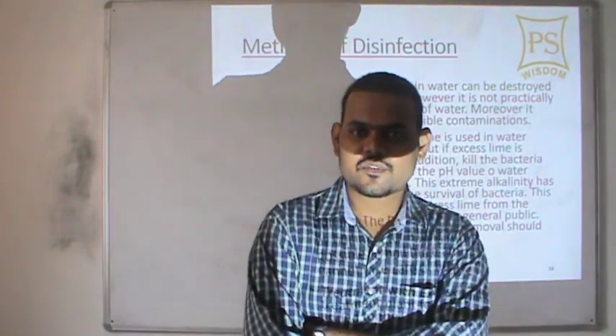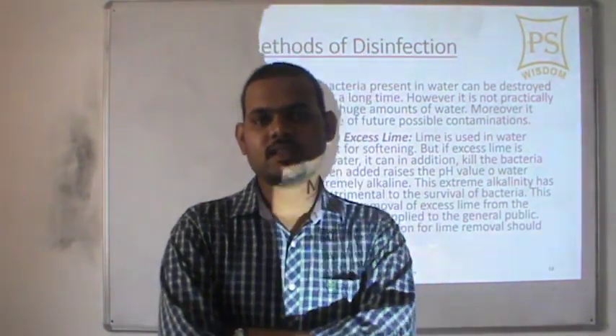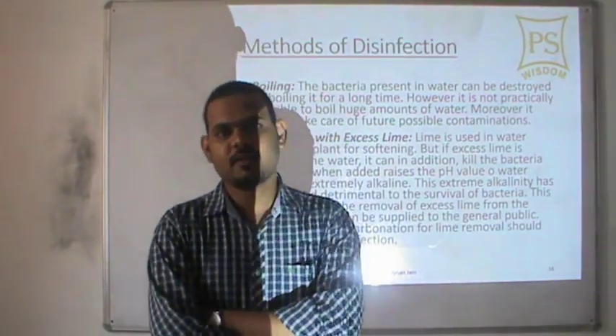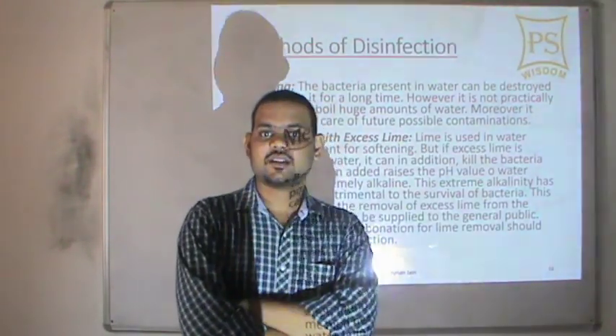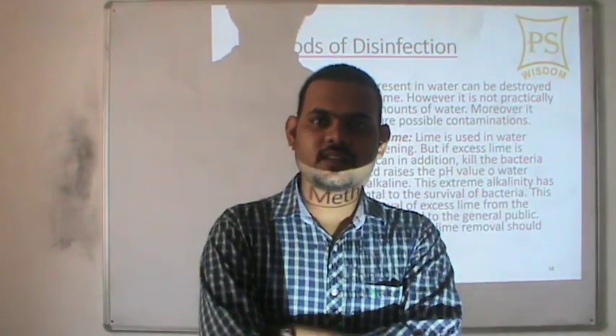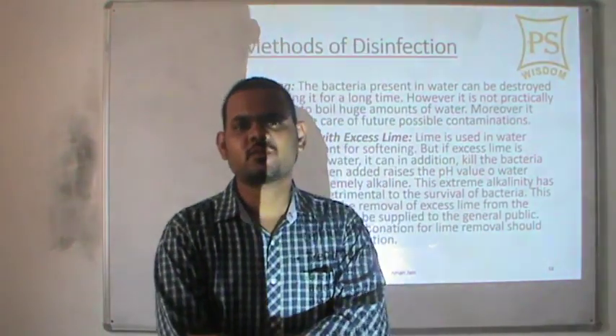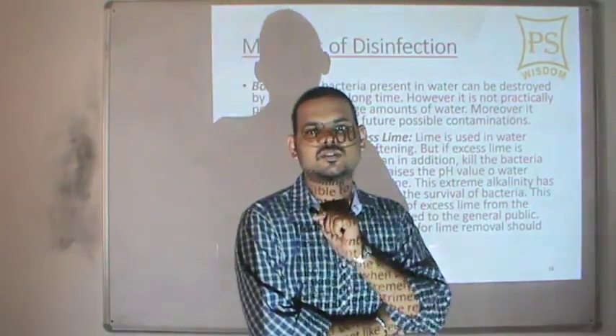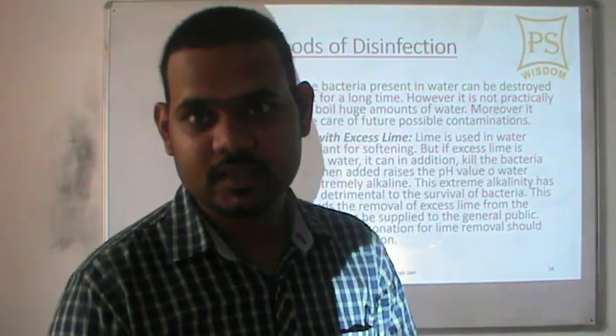Previously lime was added for softening the water; now we add some more lime to disinfect and kill the bacteria. Lime increases the pH of the water, making it extremely alkaline, and under extreme alkaline conditions the bacteria are killed. The important thing to remember is to remove the lime before distributing the water to the public. The process of recarbonation is used to remove this excess lime from the water after disinfection.